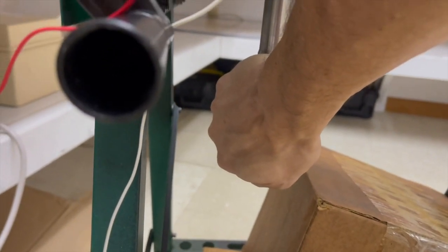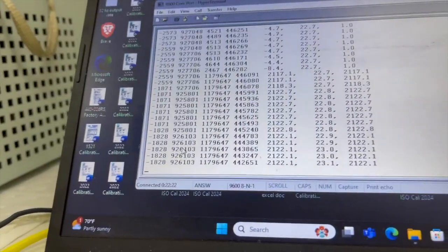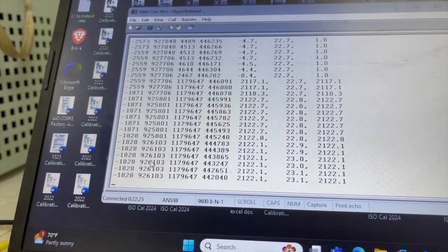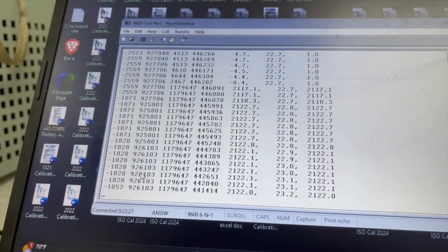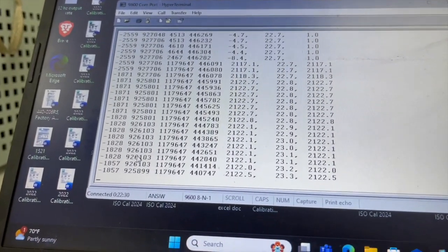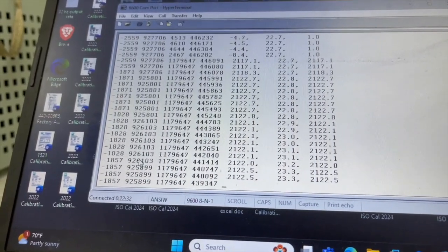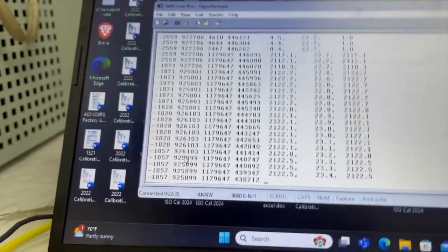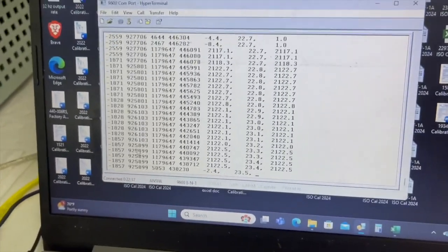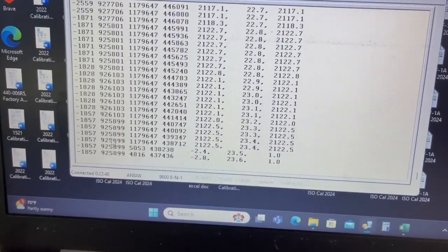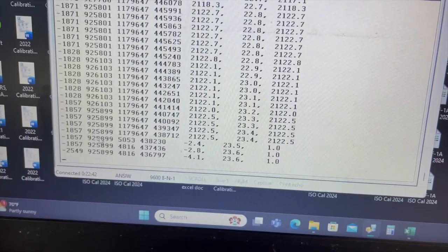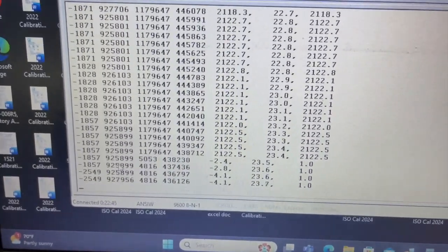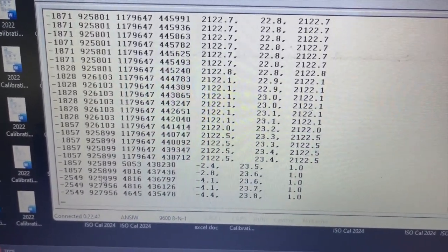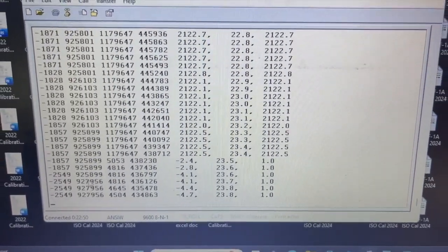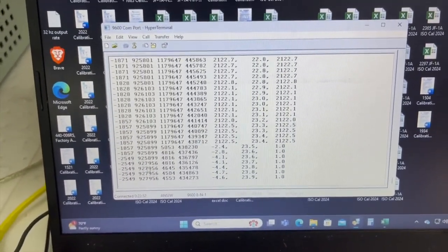And then if you hold the sensor tip with your palm like that, just grasp it completely, you should see the temperature start to rise. You can see that the temperature counts are going down, so it's dropped from 446,000 to 440,000. That tells you that yes, the conductivity is responding and working, and when I release it, you see it drops right back down. And the temperature is working because it started going up when I was holding on to it and heating it up with my hand. Okay, so that's your functionality test for the sensor.